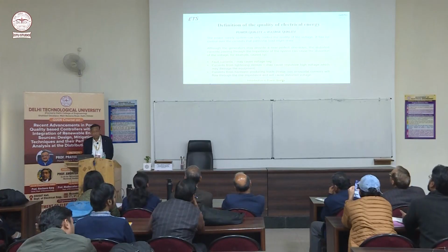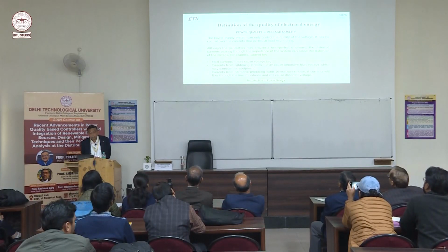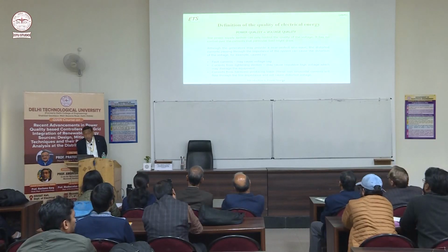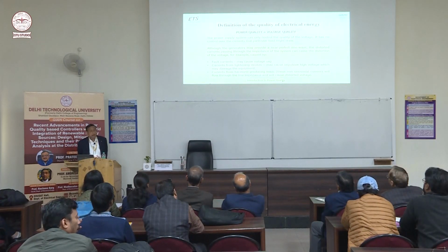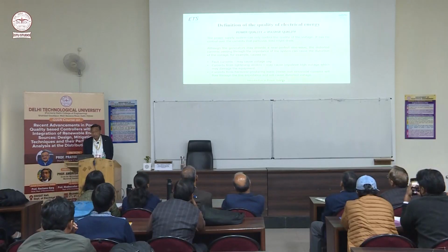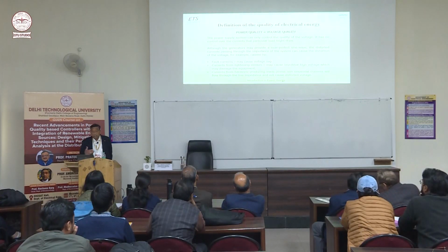Power quality equals voltage quality, as Professor Madhusudan was saying. This is what we generally say: power quality is voltage quality. So the power supply system, the utilities, can control the quality of voltage. It has no control over the currents that a particular load might draw. The generators may provide near perfect sine waves, because we have large generators. The distorted currents passing through the impedance of the system can cause distortion of voltage. If there is a fault in the line, heavy current passes through the impedance of the line, and it may cause a voltage sag.